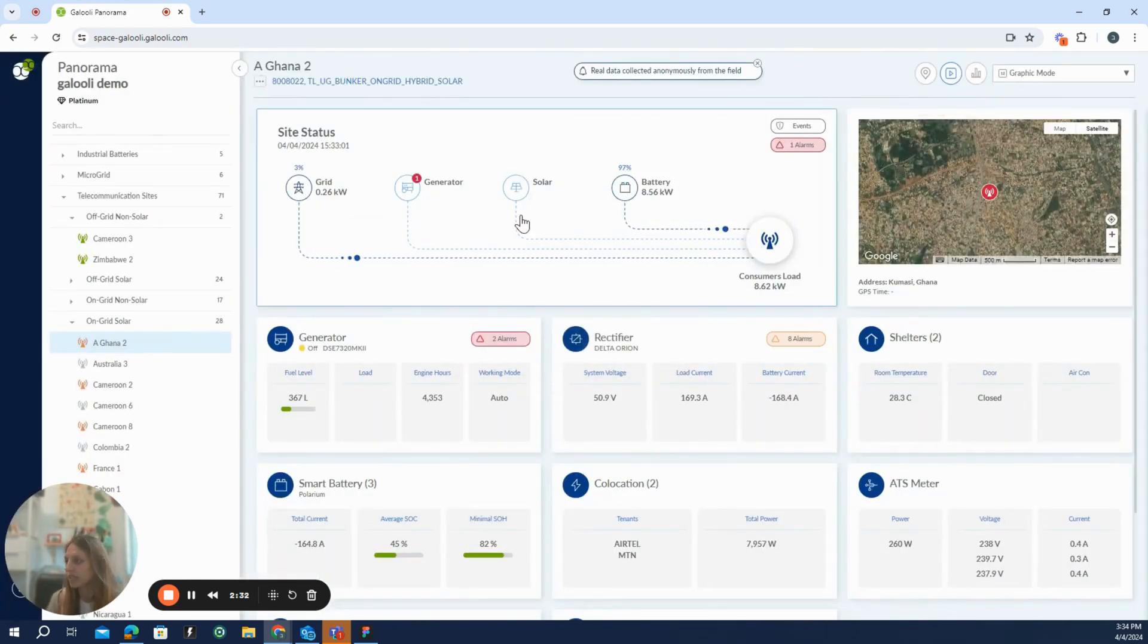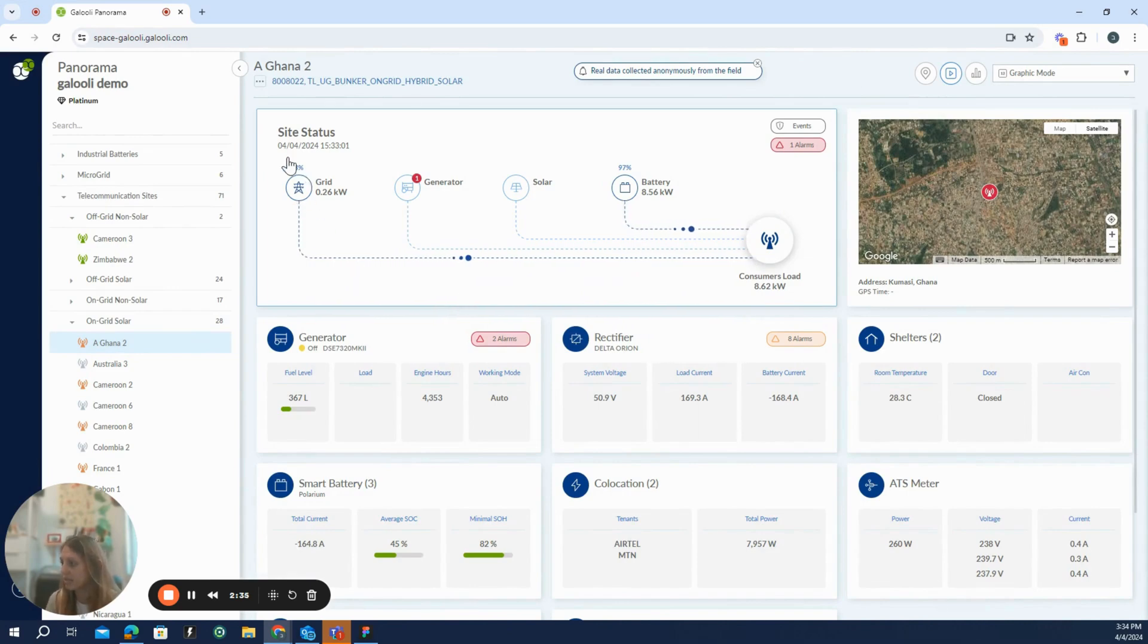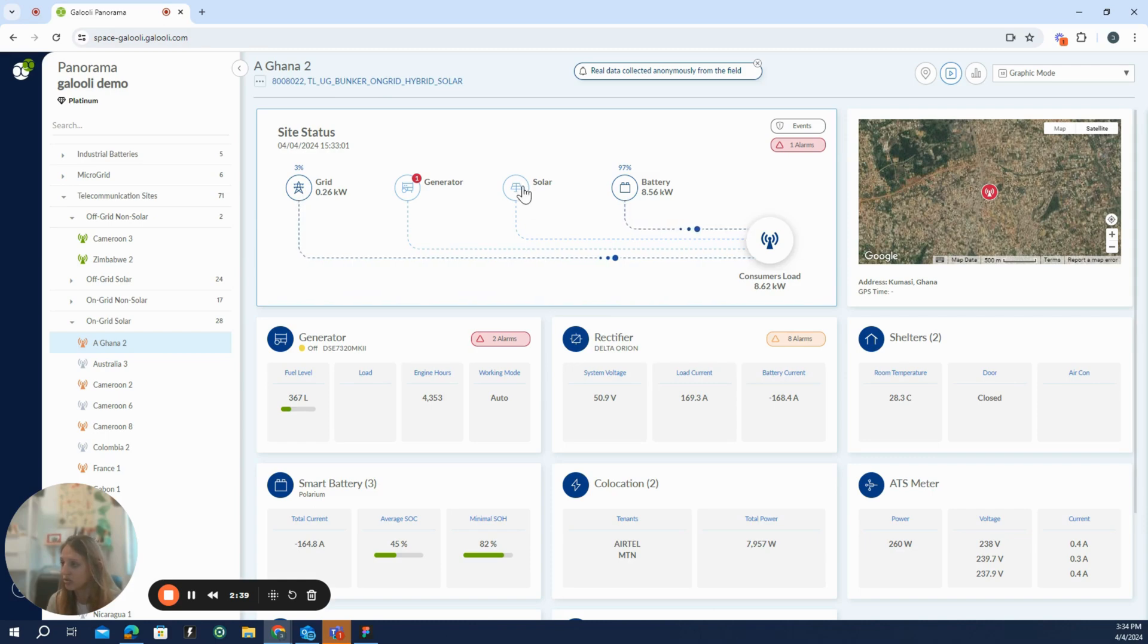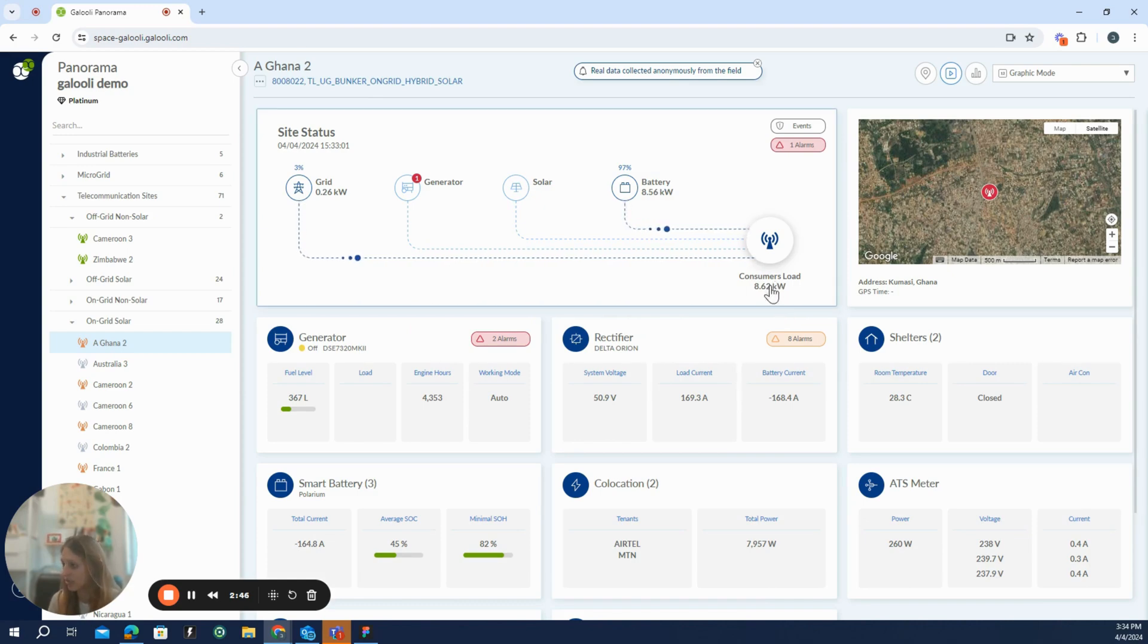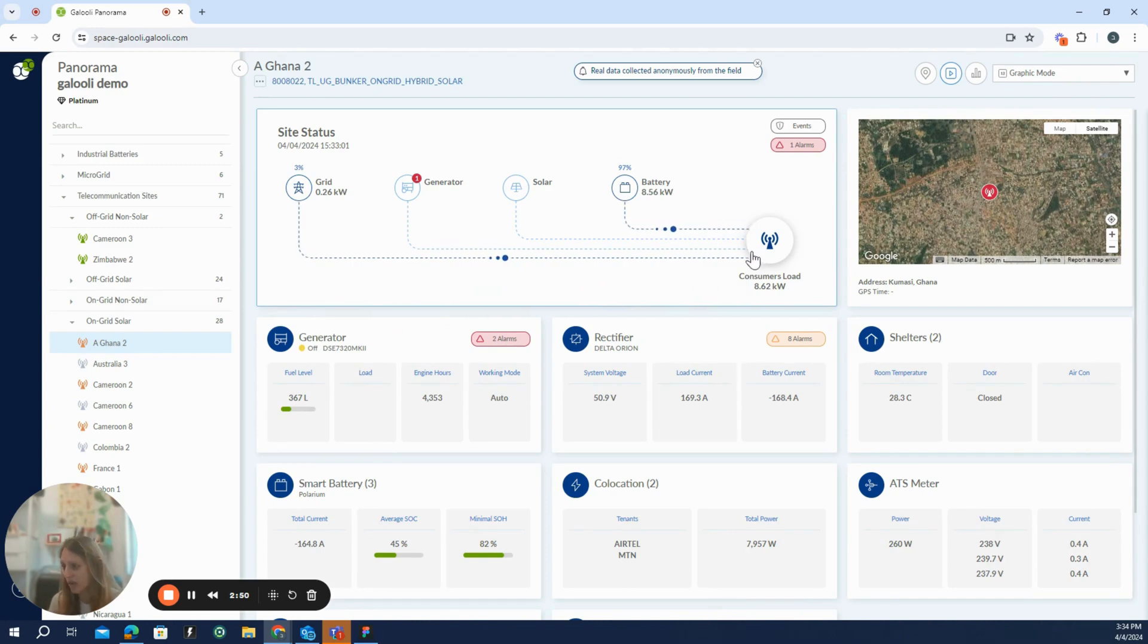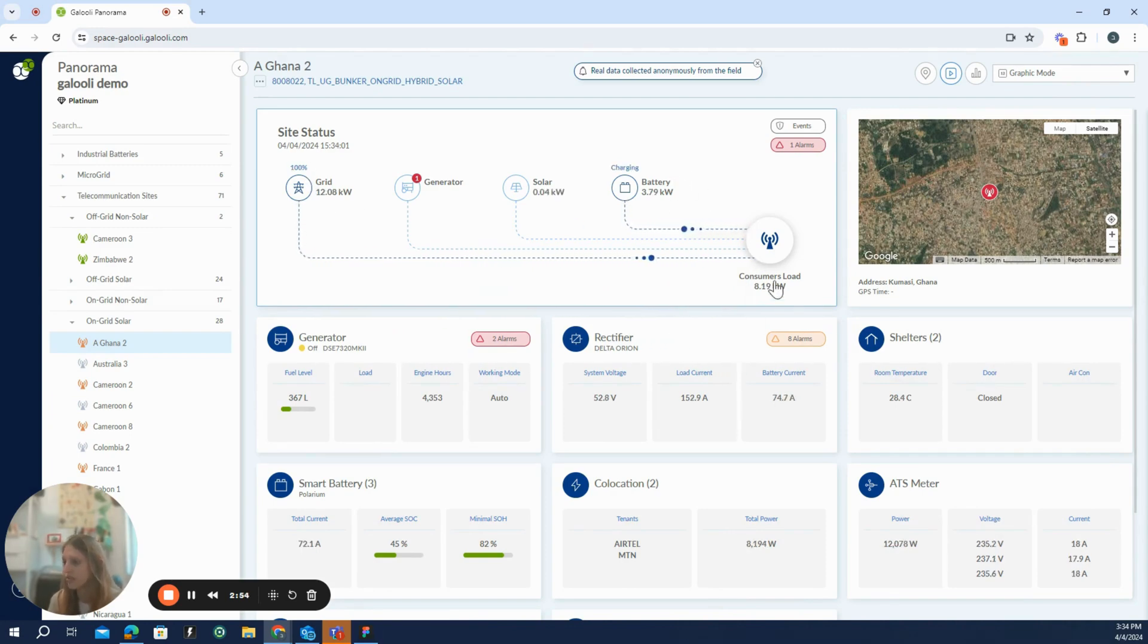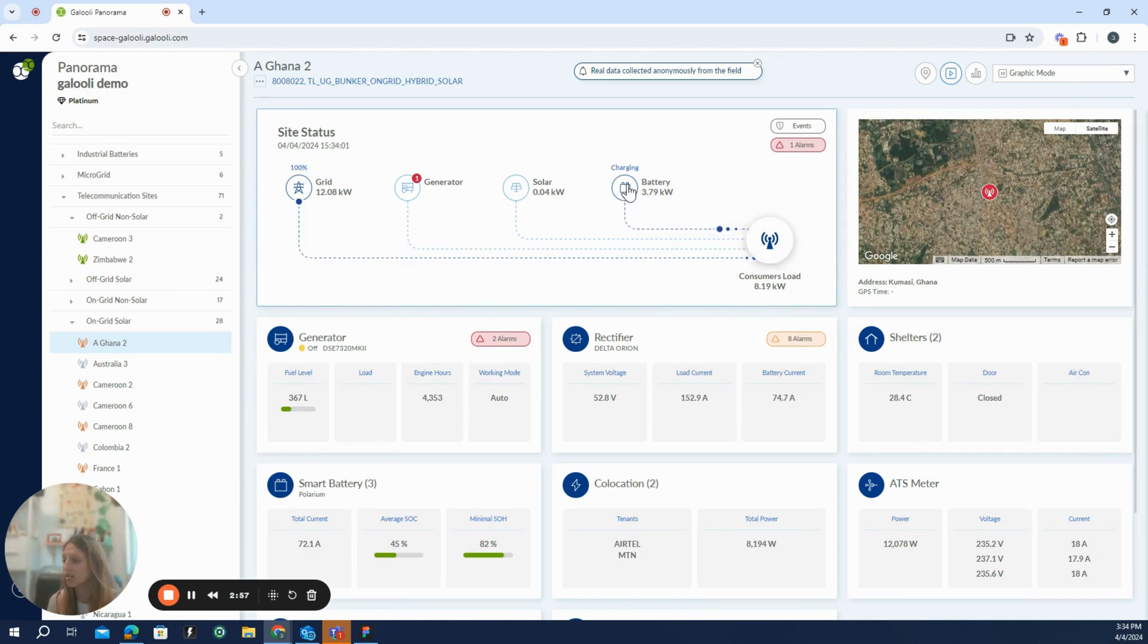Let's see what's going on with this specific unit. In this unit, we can see that we have a grid connection, a generator, solar panels, and batteries. And we see that it is consuming almost 9 kilowatts at the moment. Now we can see that the batteries are providing most of the power to the site. And now with switch, the grid is providing all the power to the site and the batteries are charging.